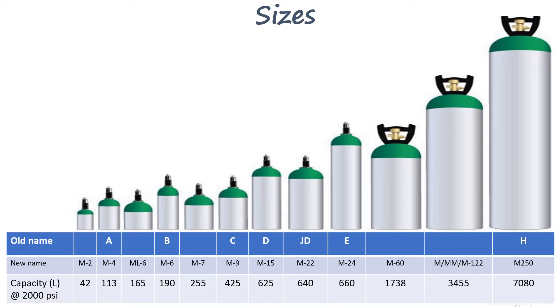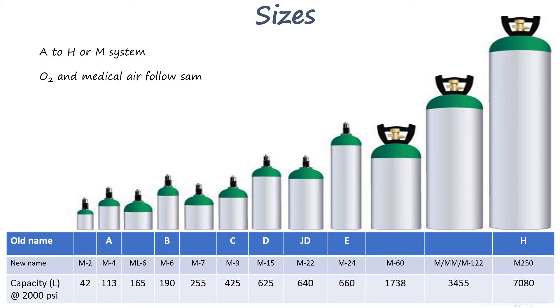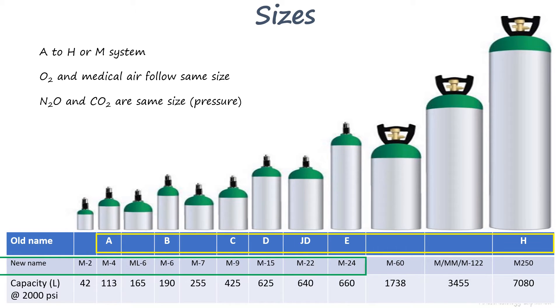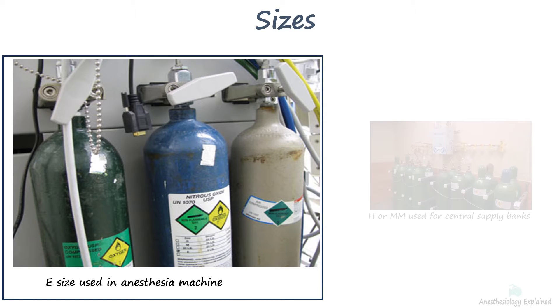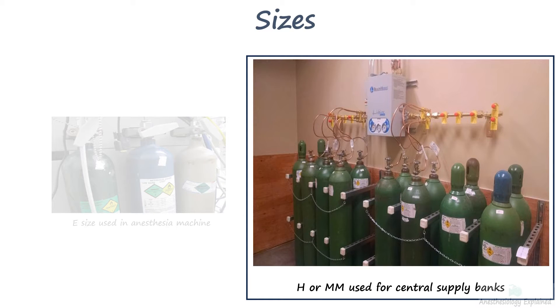The diagram below shows the different oxygen cylinder sizes and their capacity. Oxygen cylinders come in a variety of sizes and may differ slightly from supplier to supplier. Gas cylinders are labeled from A to H, with increasing volume as the letters of the alphabet proceed. The newer nomenclature uses the letter M with numbers assigned to designate the size. E-sized cylinders are the most commonly used size in medical settings, while sizes H or MM are used in central supply oxygen banks.